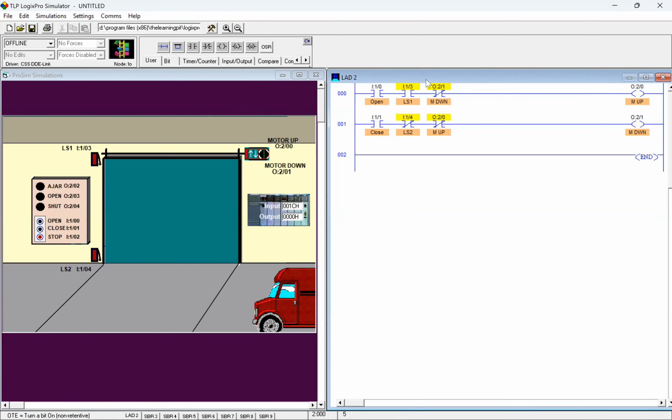And I use the normally closed contact to wire in to examine if that's open or something. And if it is open, that's great, I'm going to use it. But I would wire those in. So now not only do I have it wired out there in the field possibly, I don't have to do the wiring part because I'm going to do it through the PLC. I still have the mechanical one out there. So either way, I've got two backups on stopping that from interlocking.